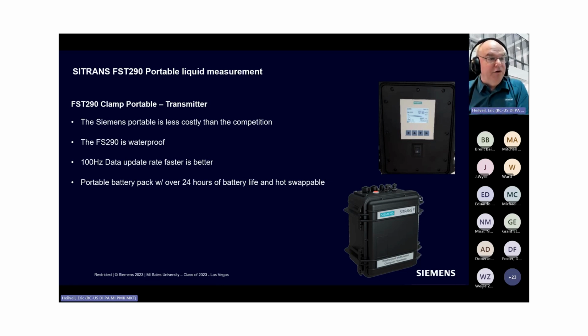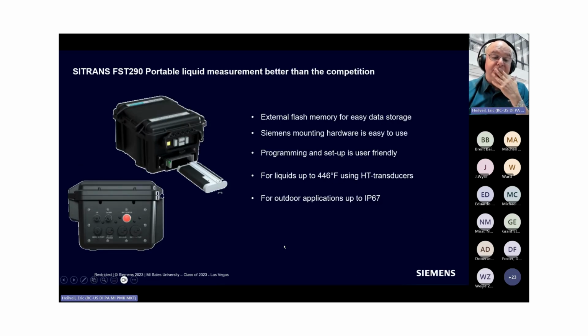So if you're measuring flow and you don't want to disturb the flow, but you've got to change the battery and you don't have an AC outlet, it's easy enough to just change batteries. You've got about 4 or 5 minutes to change them while in operation without losing power. So they can be easily hot swapped. They also have the same flash memory that we were talking about, up to 64 gigs.